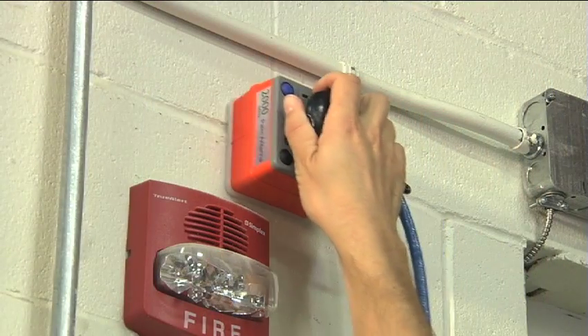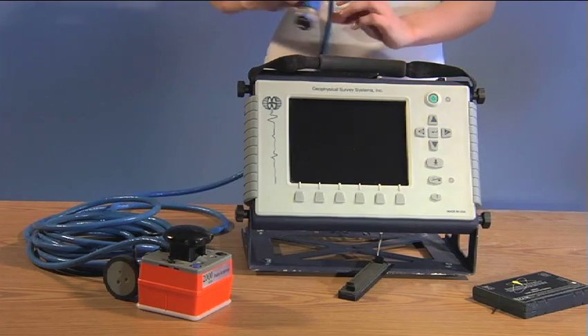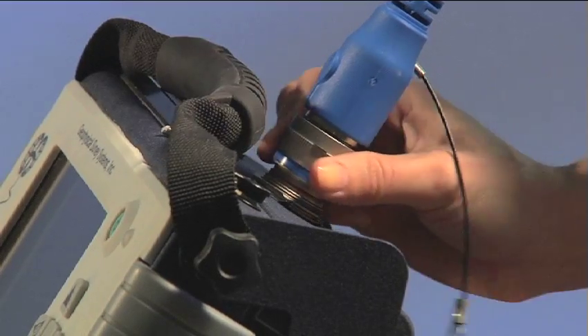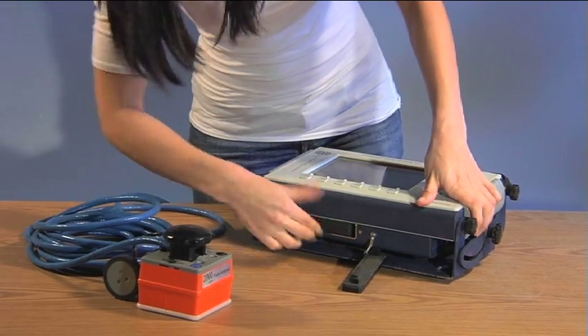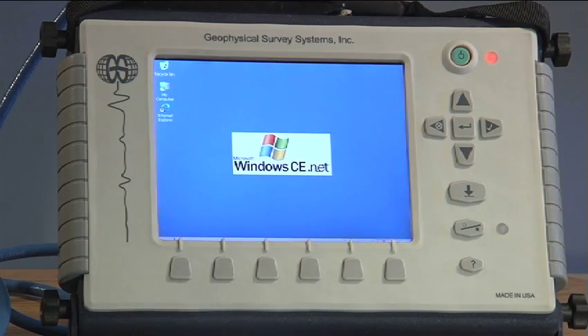The Palm antenna weighs in at approximately one pound, making it one of the most versatile tools in the StructureScan family, and it's easy to use. To set up, simply plug in the blue cable at the top of the SIR 3000 control unit. Turn on the SIR 3000 by inserting the battery. From the main menu, select Concrete Scan.